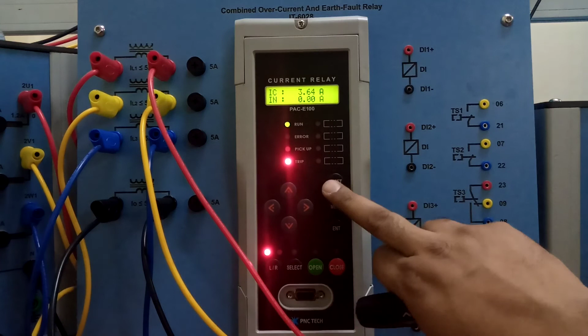Again we will increase the load on the first phase. So you see now the first phase, IA, it's now 3.88, and there is a pickup, and there you go, the relay has been tripped. So this is how it works.